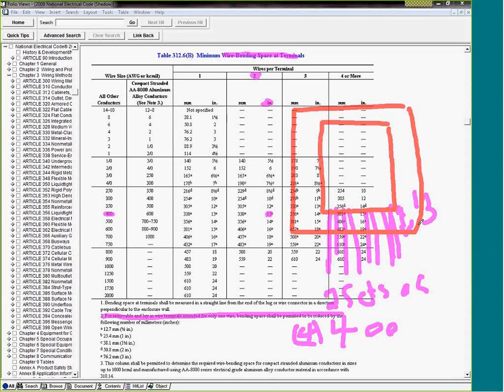Anybody have any question about how to use this one? That's basically the bending space. They need this space to be able to bend your conductors. You bend them since they are not going in at an angle. You're going to be bending them to tie them to the circuit breaker. I want to bring to your attention, my friend, that right in here there will be circuit breakers or lugs, each one will be tied, and there will be the neutral tied to the neutral, right? And we terminate these. These are very important tables, and don't forget to use them.